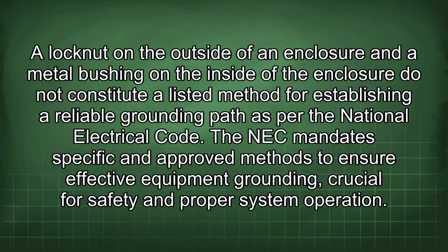A lock nut on the outside of an enclosure and a metal bushing on the inside of the enclosure do not constitute a listed method for establishing a reliable grounding path as per the National Electrical Code. The NEC mandates specific and approved methods to ensure effective equipment grounding, crucial for safety and proper system operation.